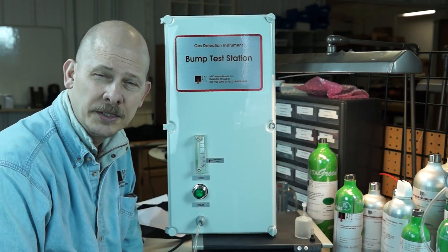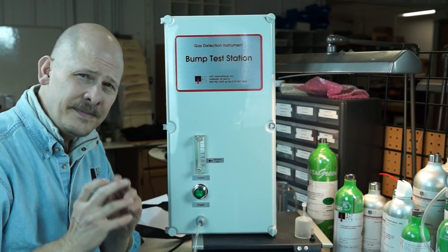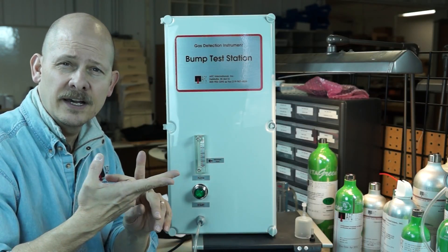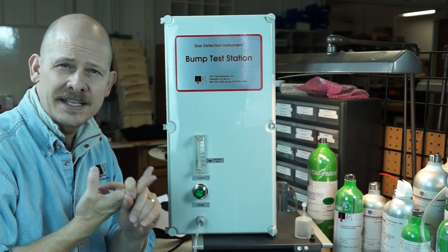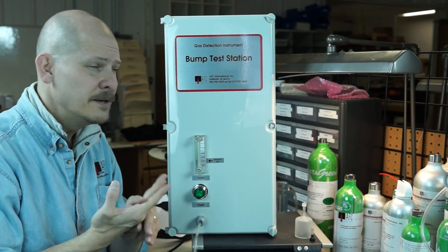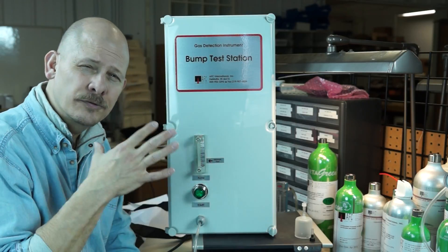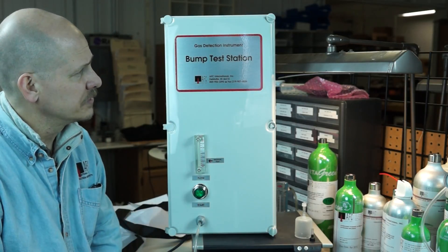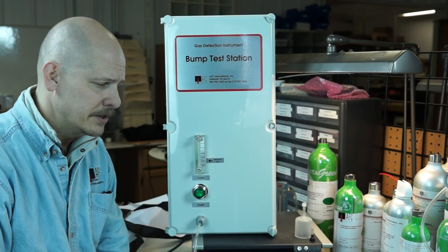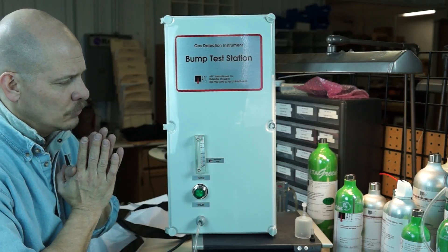The BTS 101 — this is our first model, the original — is a universal gas monitor bump test station. The whole point is to quickly, efficiently, and safely bump test virtually any make or manufacturer of gas detector on the market today. It doesn't matter if it's a diffusion unit like the RAE Systems ToxiPro for carbon monoxide or a multi-gas meter like the Dräger X-am 2000 — it covers combustibles, oxygen, CO, and H2S.